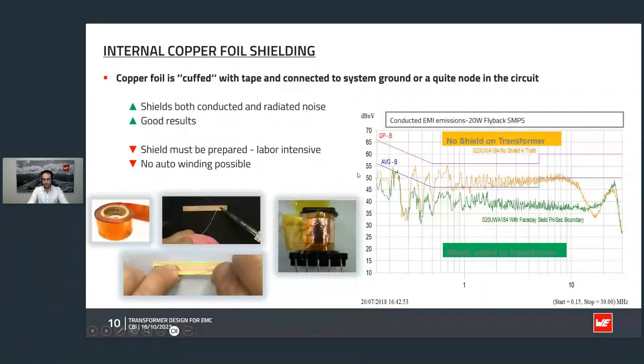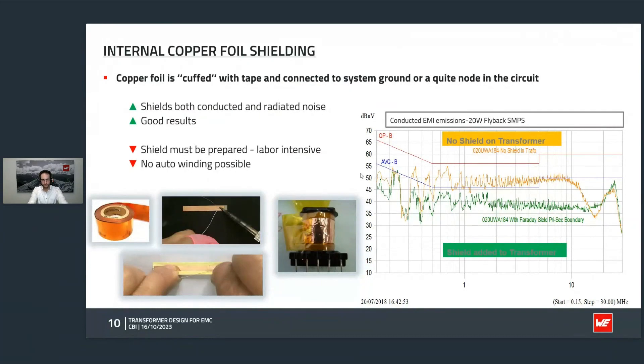If the EMI behavior of the transformer is still not good enough and we need to further improve it, we can try to insert a shield winding. Here we talk about an internal shielding, which means the shield winding is positioned between the primary and the secondary. In this case it is a copper foil. You see in these pictures how it is manufactured — first the operator solders a lead wire to one end of the foil so we can later connect the start of the foil to a stable potential, for example ground. Then the foil is wrapped into insulation tape and inserted into the transformer.